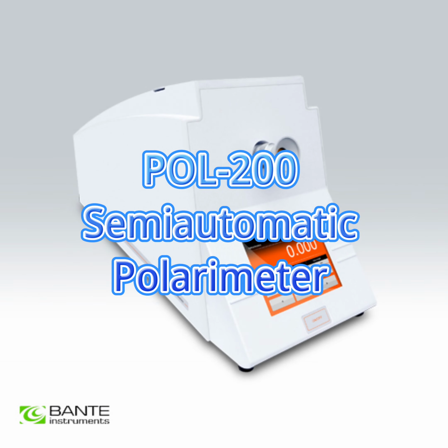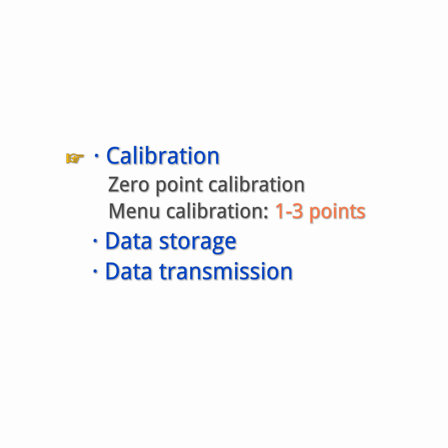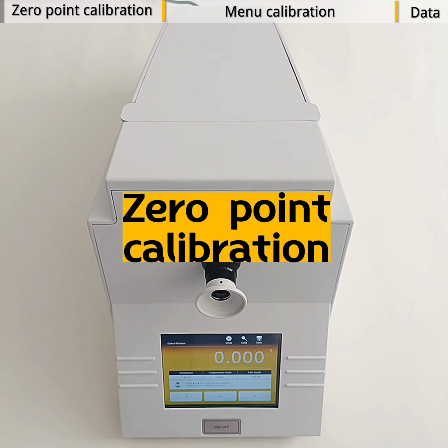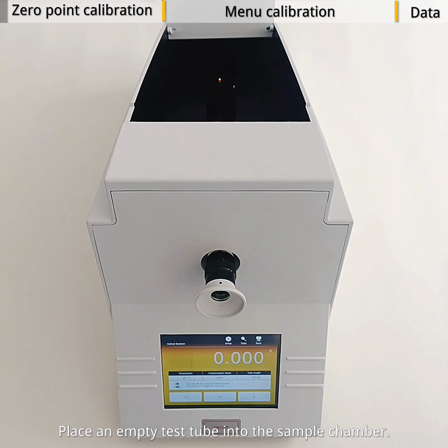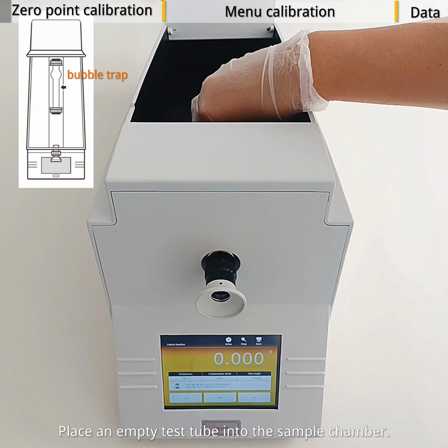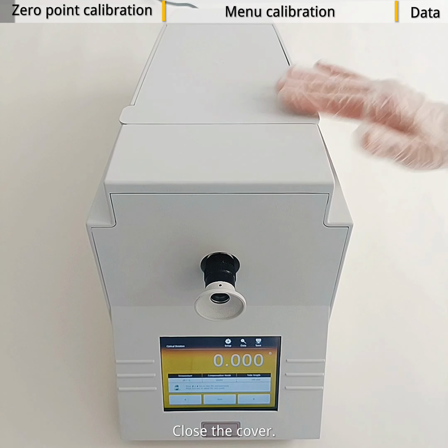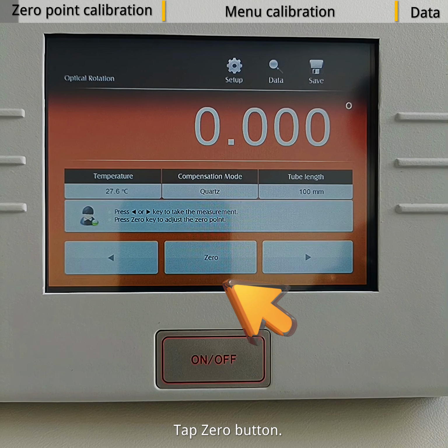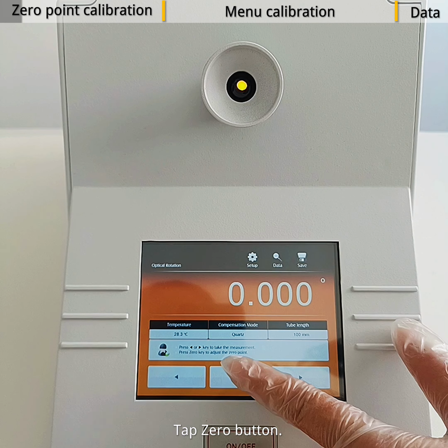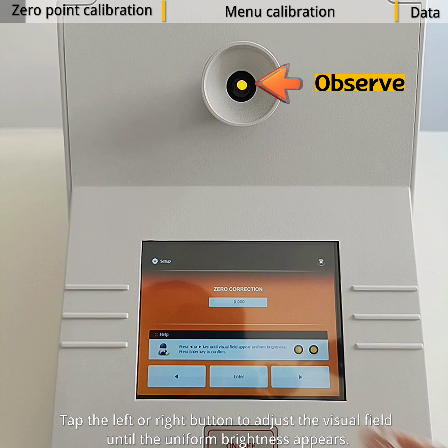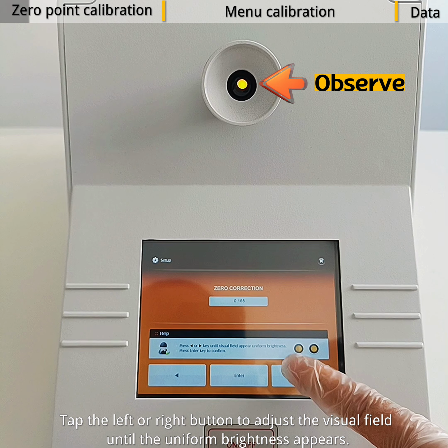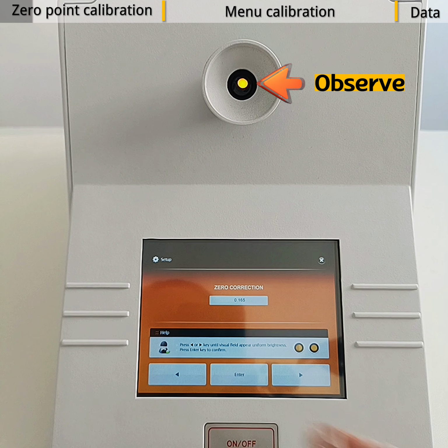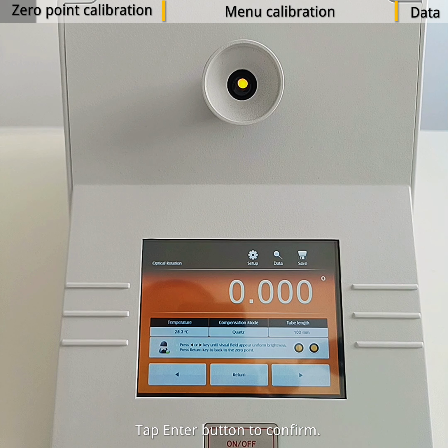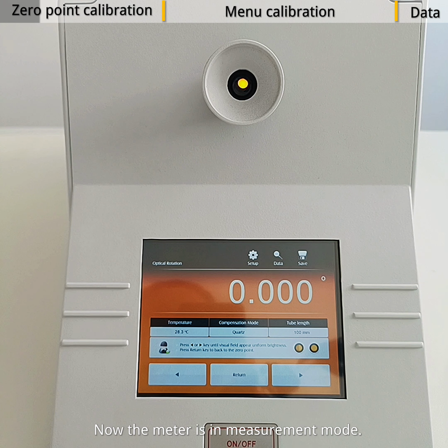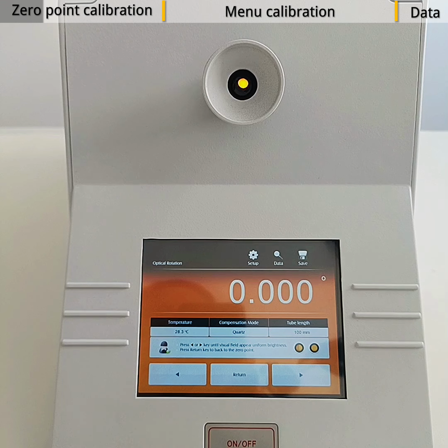POL200 semi-automatic polarimeter: calibration, data storage, data transmission. 0-point calibration. Place an empty test tube into the sample chamber. Close the cover. Tap 0 button. Tap the left or right button to adjust the visual field until the uniform brightness appears. Tap Enter button to confirm. Now the meter is in measurement mode.